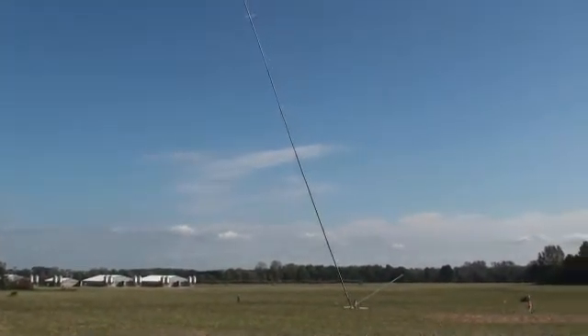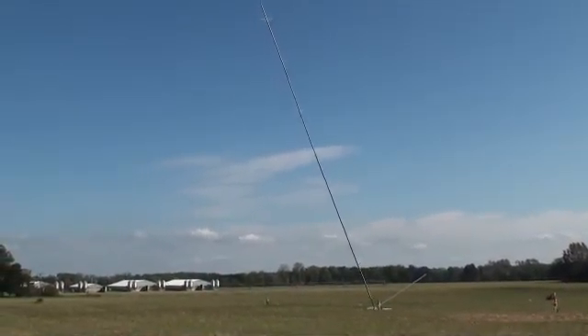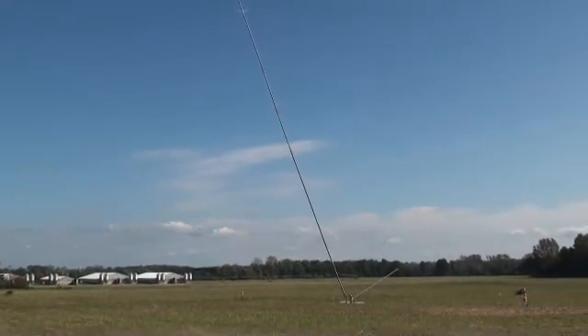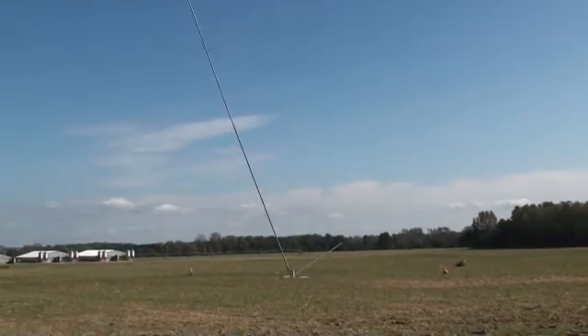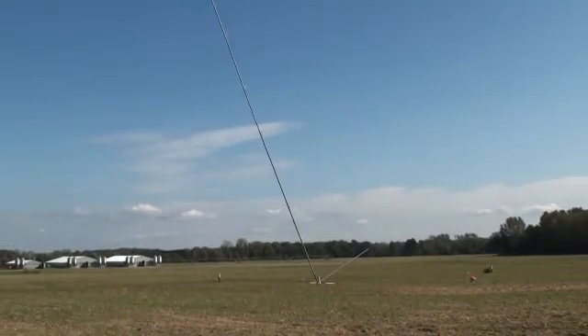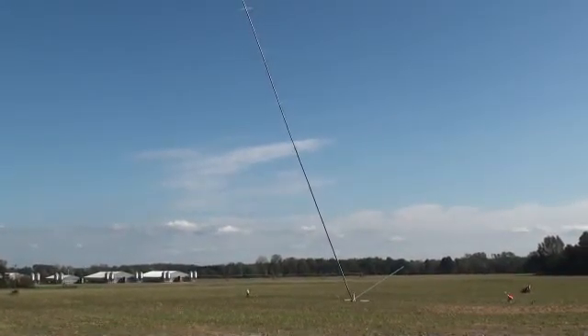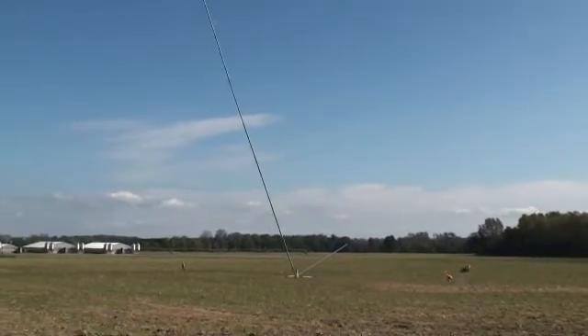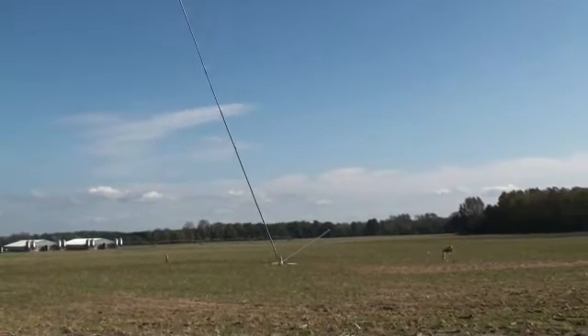If we end up putting up wind turbines here, the wind turbines are going to be about 80 to 100 meters to their hub, which is the center of their blades. Because that tower is going to be 60 meters high, you've got to figure out a way to project what those velocities are going to be at the higher elevations. You do that by looking at the wind speeds at the varying elevations and mathematically projecting what the wind speeds at the higher elevations are going to be.